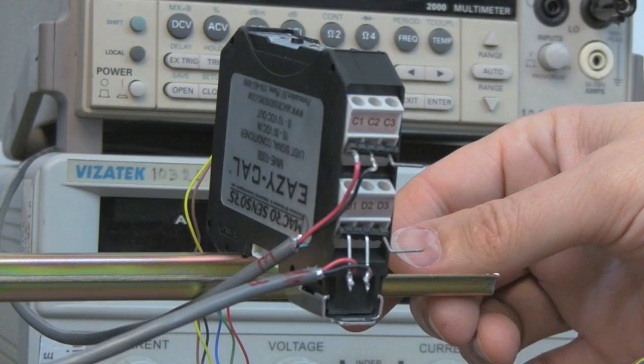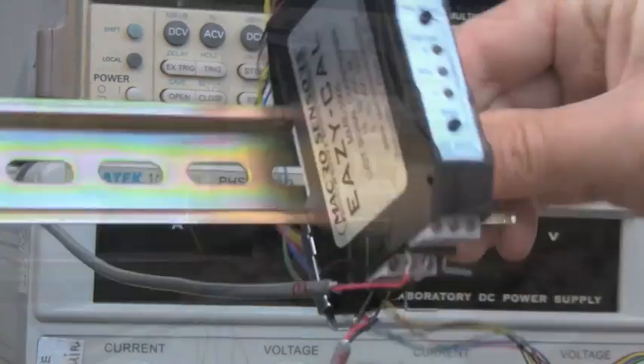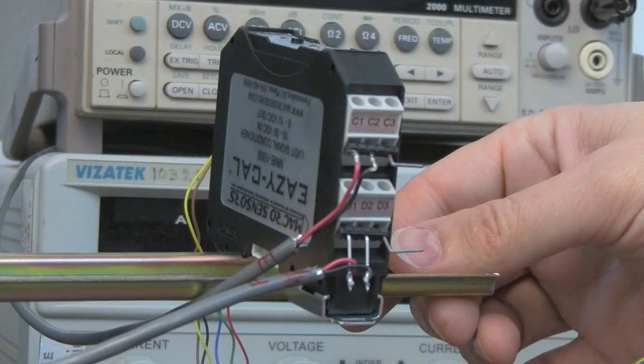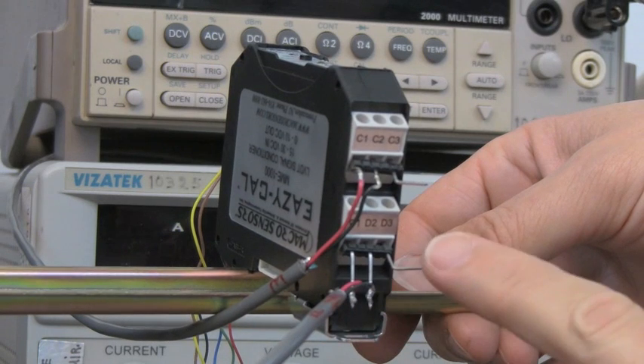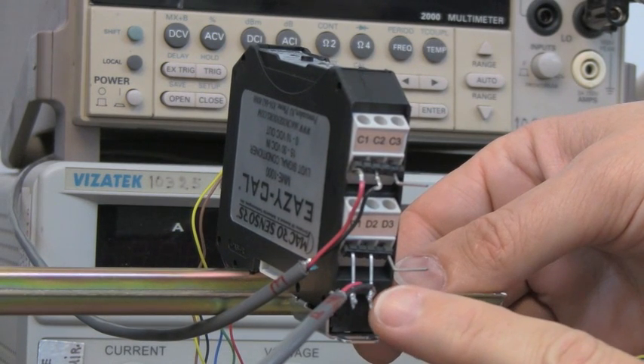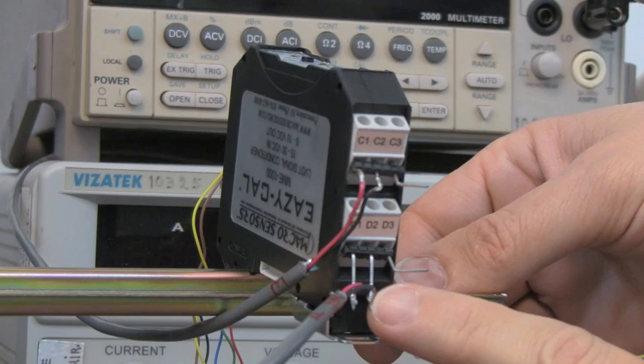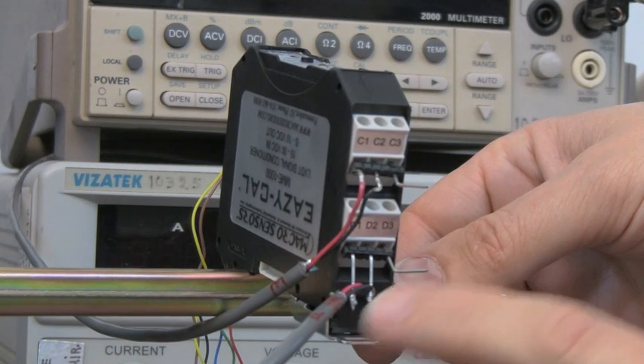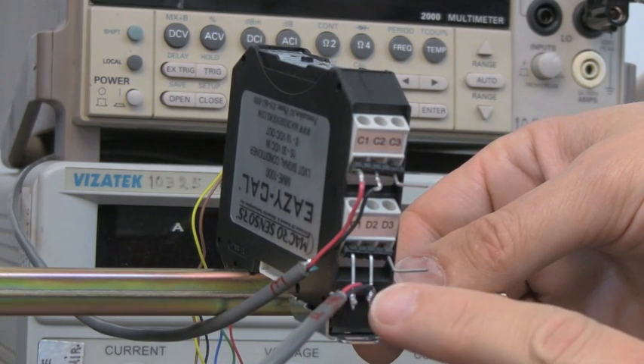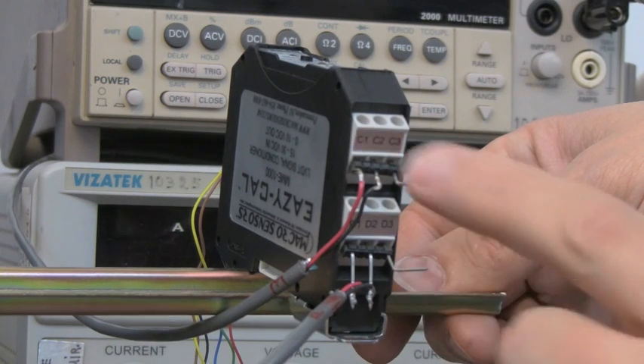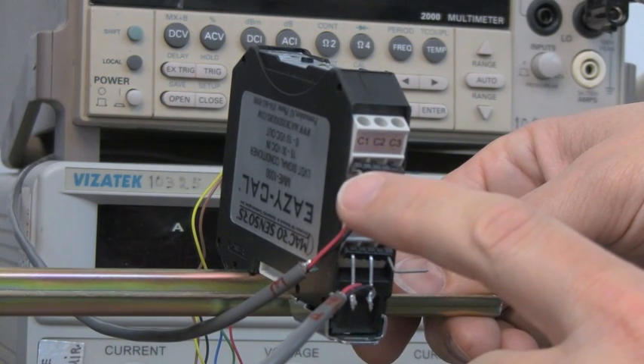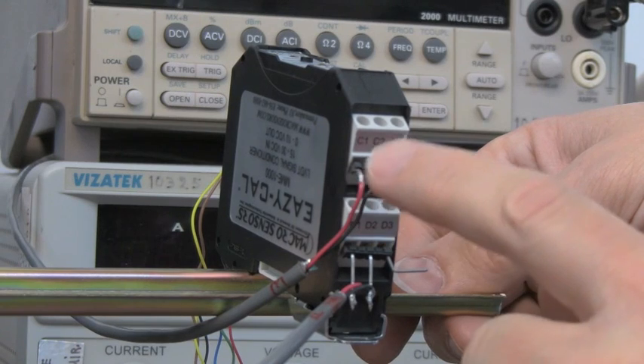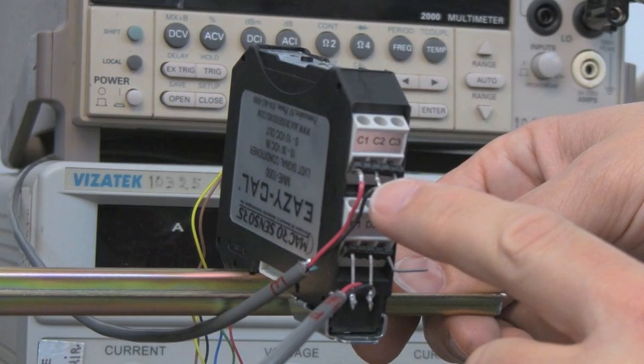All of the input and output voltage connections are made on the bottom side terminals, while the LVDT is connected to the top side terminals. Looking at the bottom side, the supply voltage has been connected to terminals D1 and D2, with plus 24 volts DC going to terminal D1 and ground, or 0, going to terminal D2. The digital voltmeter, which will read the voltage output of the EAZY-CAL, has been connected to terminal C1, which is the positive DC voltage output, and to terminal C2, which is ground, or 0.